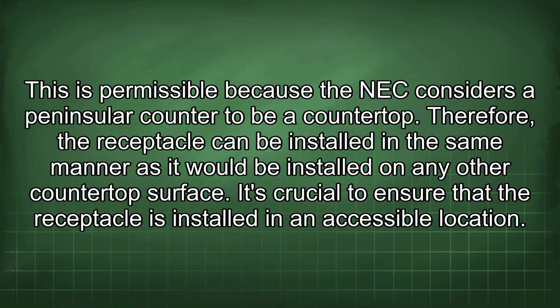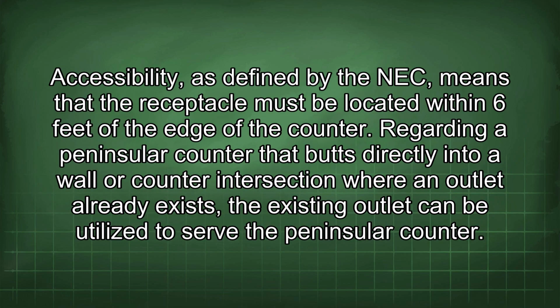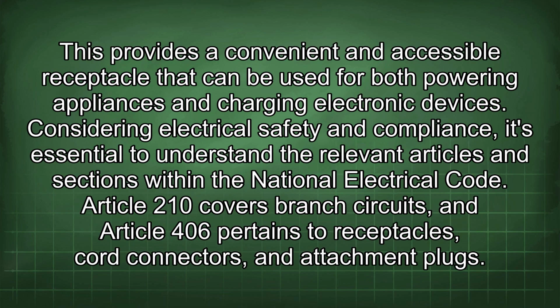It's crucial to ensure that the receptacle is installed in an accessible location. Accessibility, as defined by the NEC, means that the receptacle must be located within 6 feet of the edge of the counter. Regarding a peninsular counter that butts directly into a wall or counter intersection where an outlet already exists, the existing outlet can be utilized to serve the peninsular counter. This provides a convenient and accessible receptacle that can be used for both powering appliances and charging electronic devices.